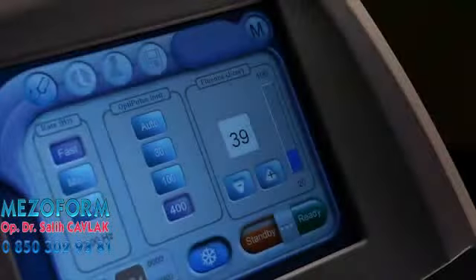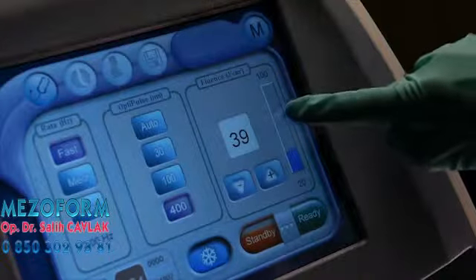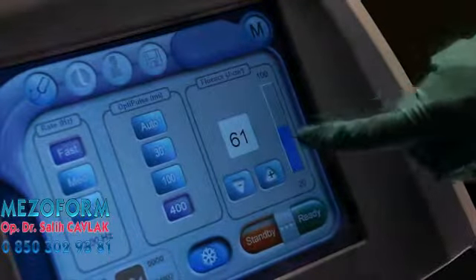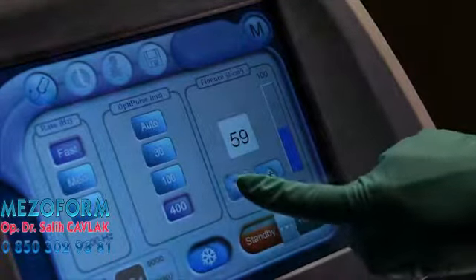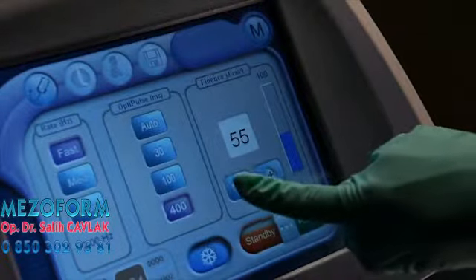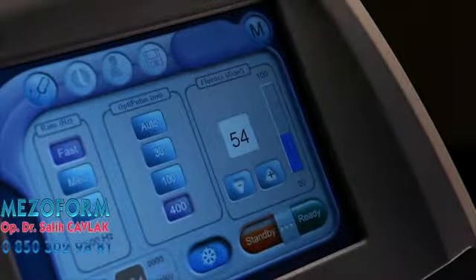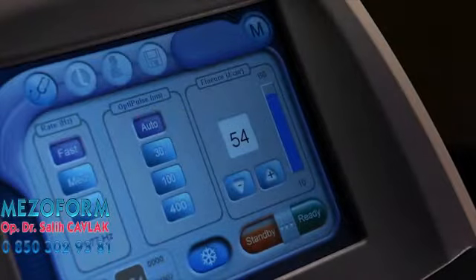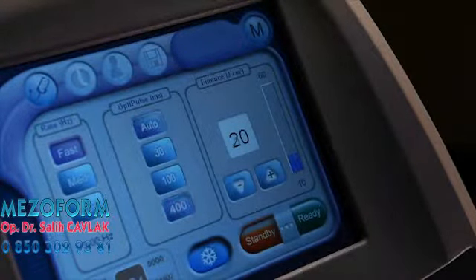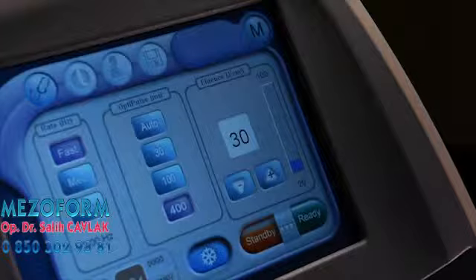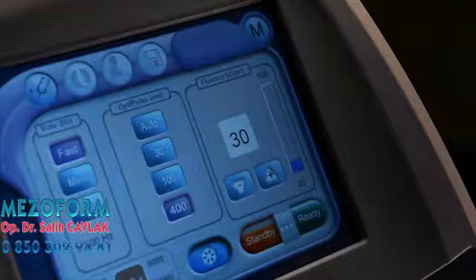The fluence can be selected numerically or by touching the bar on the treatment screen. The highest tolerable fluence will provide the greatest efficacy. Auto, 30 millisecond and 100 millisecond will allow up to 60 joules per centimeter squared. 400 millisecond pulse duration will allow up to 100 joules per centimeter squared.